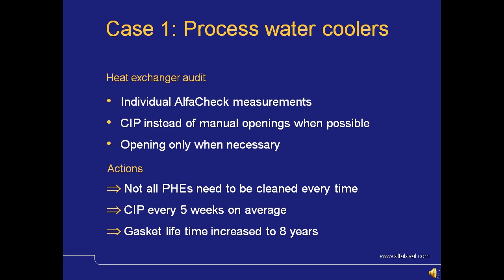In order to help the customer optimize the maintenance process, Alfa Laval did a heat exchanger audit. We did individual AlfaCheck measurements, which is a performance measurement done on a heat exchanger still running, to see how fouled it is and to see whether or not it needs to be cleaned. The proposition was to do CIP, the chemical cleaning of the heat exchangers, instead of manual openings when possible. This is much less time consuming and cheaper. Also, it does not involve as many people in the maintenance procedure.